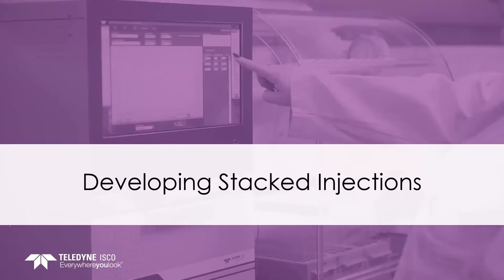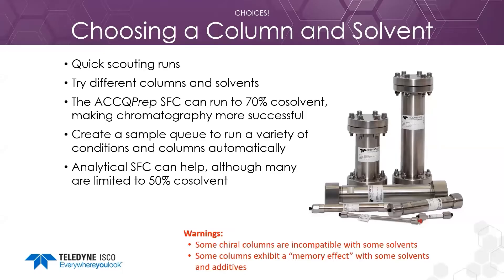Developing stacked injections has two parts: screening columns and solvents, and then determining the mobile phase composition and loading. The first step is choosing a column and solvent — you run different combinations and choose the best one. This is often done even if you aren't running stacked injections, just to get the best chromatography for a compound. Screening can be done on an analytical system, but many are limited to 50% co-solvent, while the ACCQPrep can run up to 70% co-solvent reliably. Make sure the co-solvent is compatible with the column.